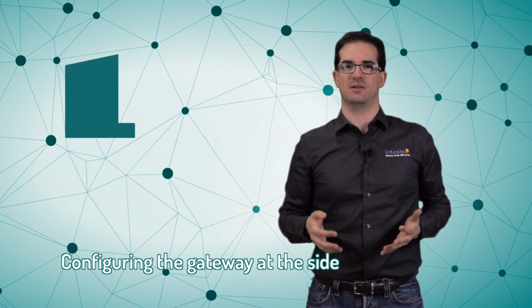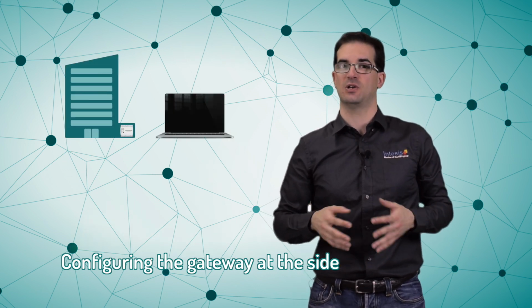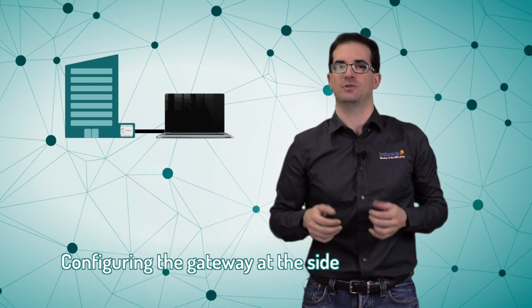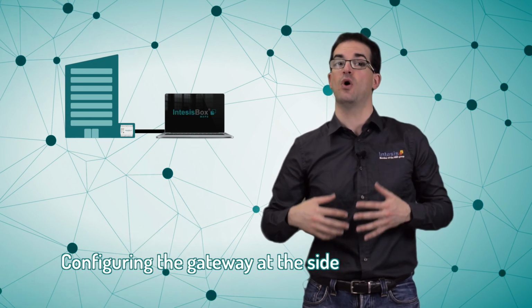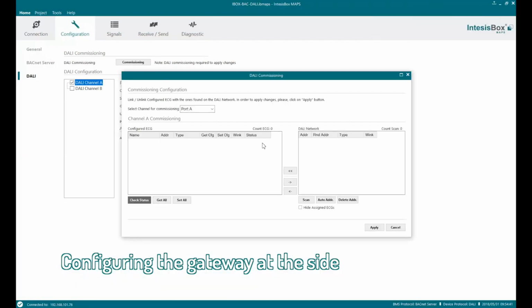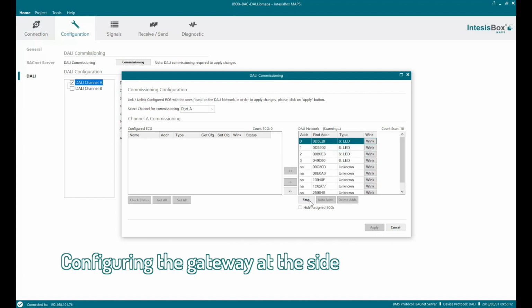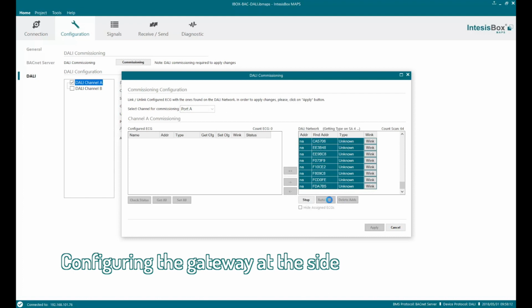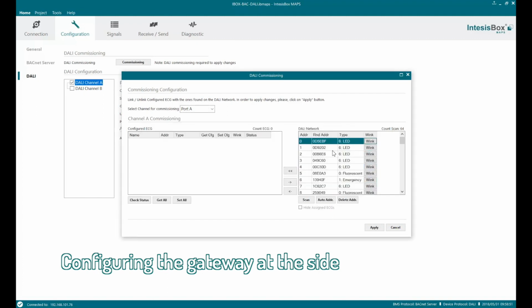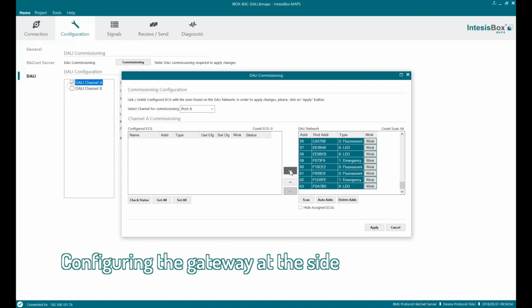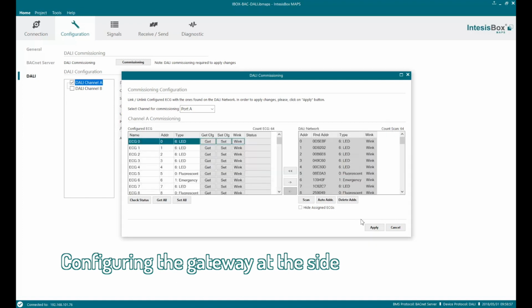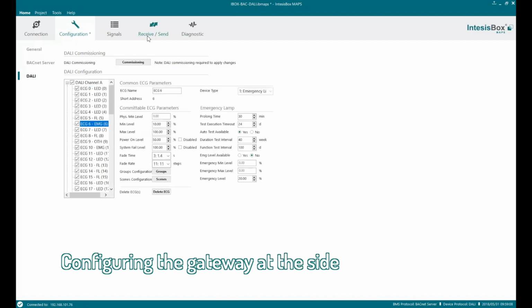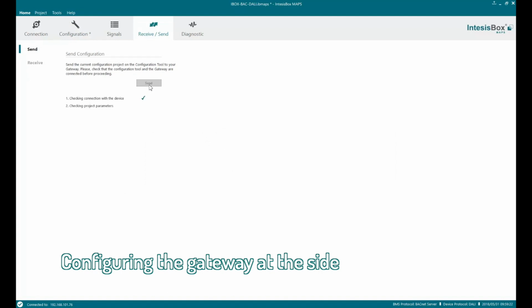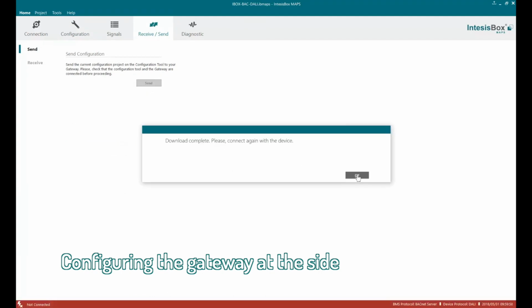Now imagine that you have a DALI installation, and you have access to this DALI installation. It's also a new project, but you can connect to the DALI bus. So you just go right there with IntesisBox Maps software. Then you open the commissioning tool, and you can scan the DALI bus. You will get a list of all the DALI ECGs available right there. Probably, some of these ECGs discovered in the commissioning tool will be unaddressed, so just with a random address. This is not a problem, as with our software we can give the short address to all of them just by selecting all of them and then clicking auto address. Finally, you just have to add all these devices to our project in Maps, apply the configuration we want, and project done.